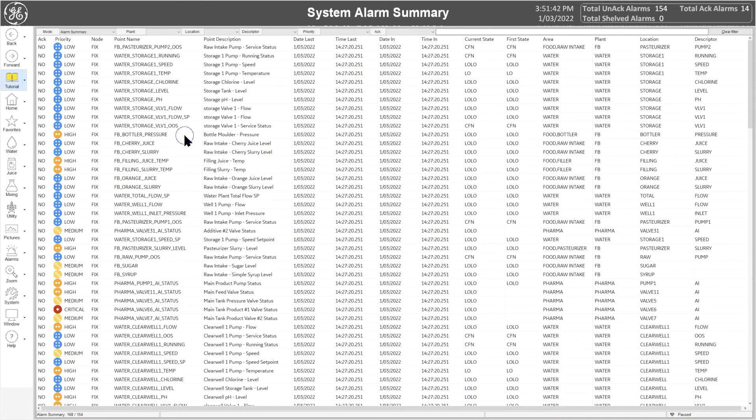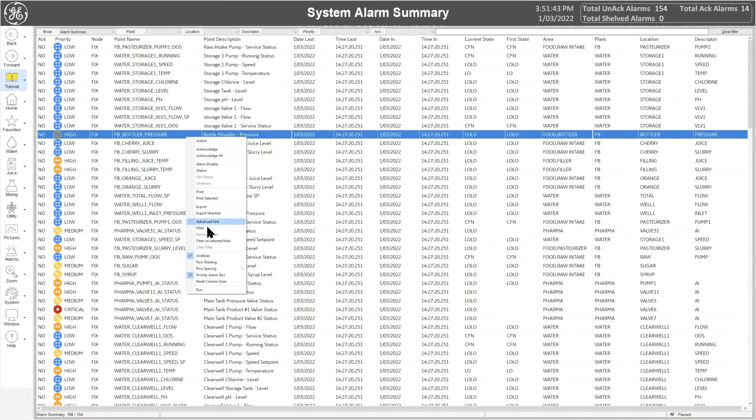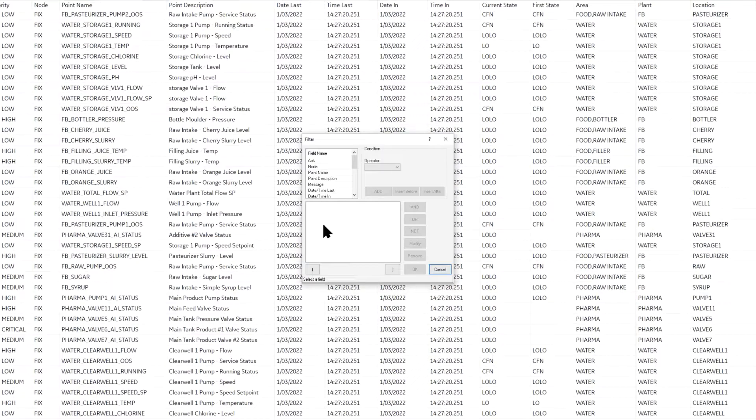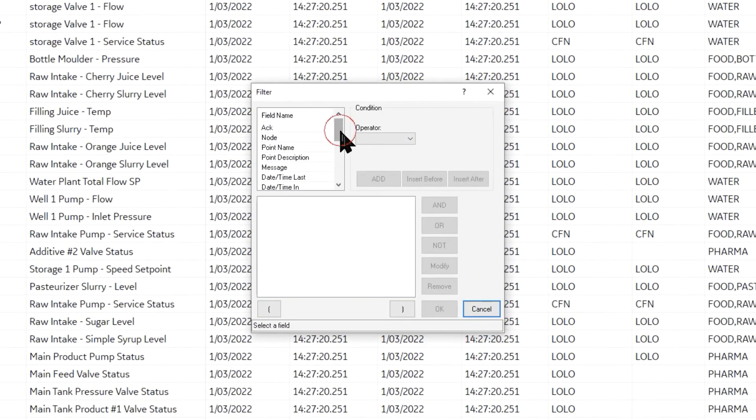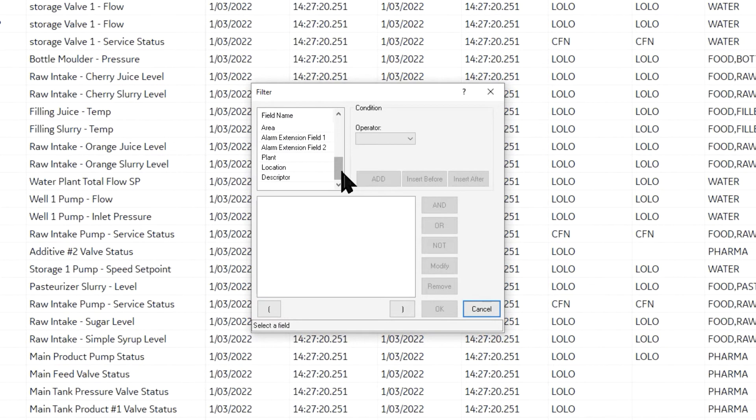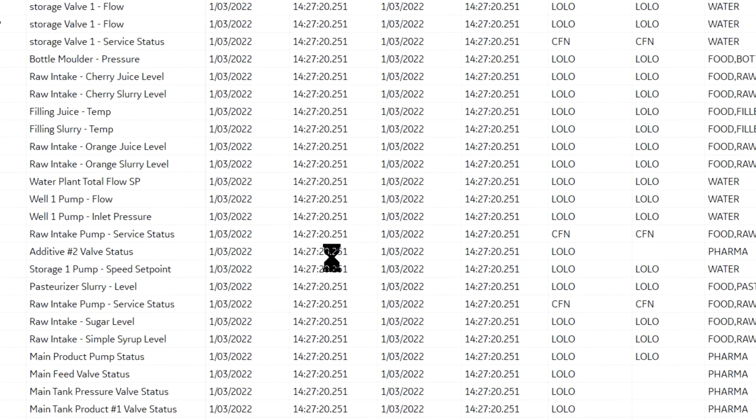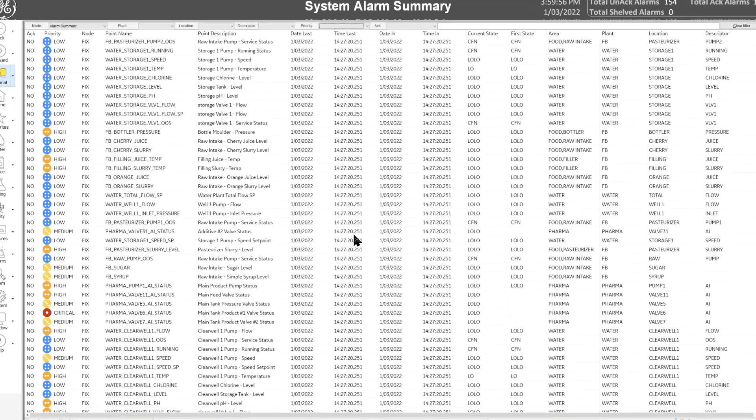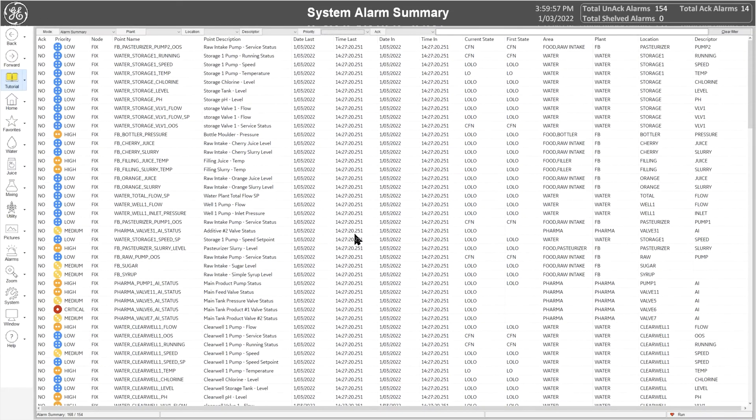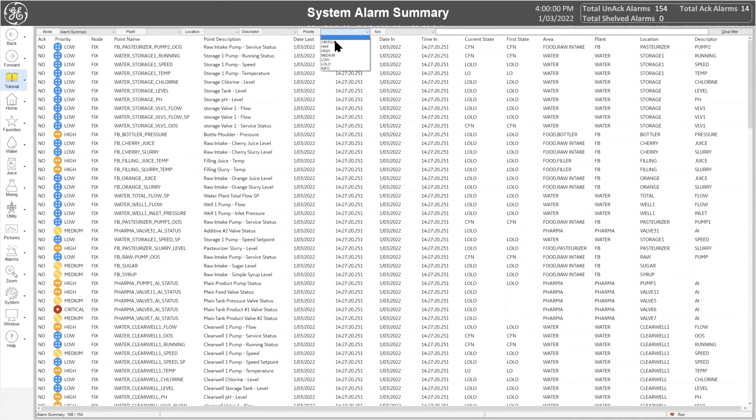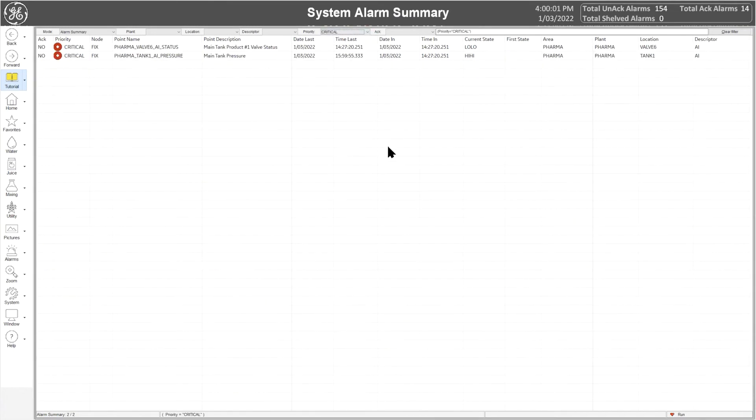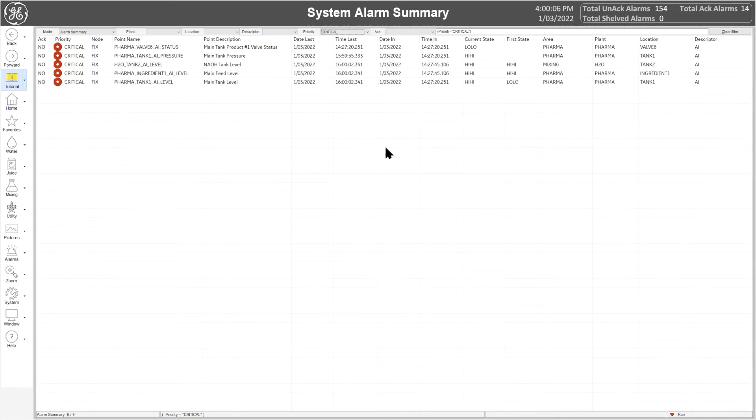You can also create advanced filters that make use of all the available fields within the Alarm Summary. This quick filter feature is vital to alarm management, as it minimizes distracting or nuisance alarms to operators, allowing them to easily focus only on the most critical alarms.